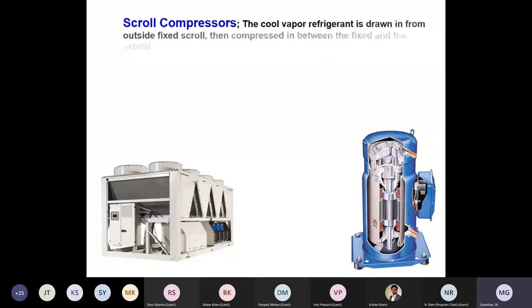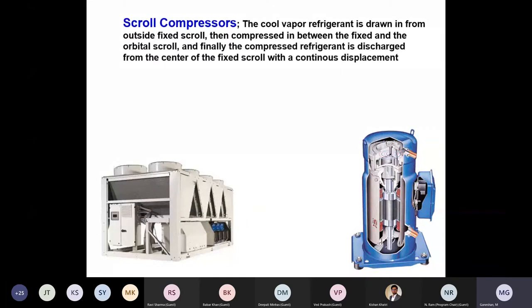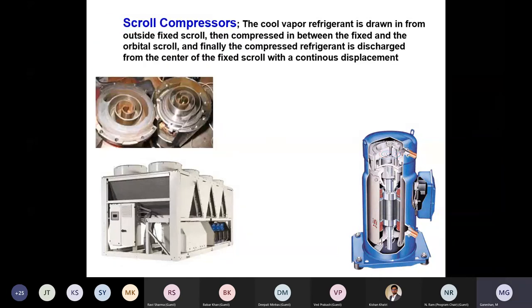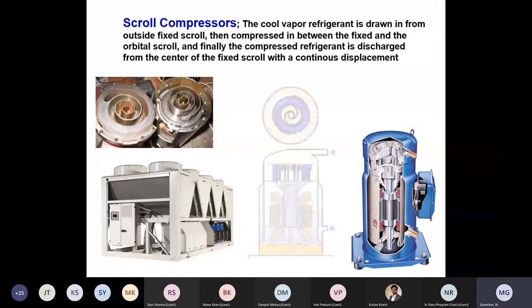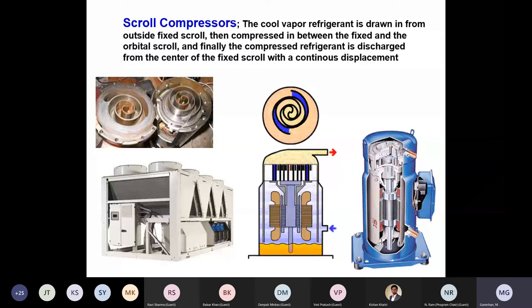Okay, so let's go into the scroll compressor. Basically, it draws refrigerant from the outside fixed scroll, then compresses it in between the fixed and the orbital scroll. Finally, the refrigerant drawn from outside is compressed into the center, and then the hot discharge gas comes out. This is how it functions. We call these scroll compressors, and they are used in many applications nowadays.